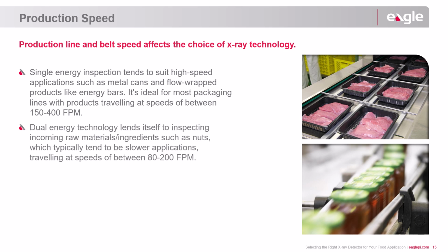Dual-energy X-ray technology is more effective for products from natural sources like bag salads, where contaminants are naturally occurring non-organic and imaging is complex due to low density and water content.